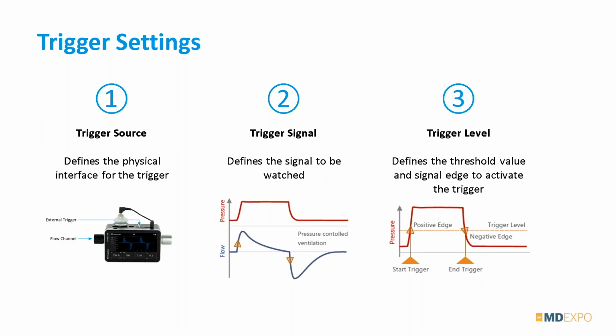There are a handful of ventilators on the market that have a trigger output. They can tell you with a digital signal when they start an inspiration phase and when they change to exhalation, so you can also use that digital signal. But very typically you have a measurement on the gas flow analyzer that you want to use for triggering. Then you can select the signal, typically the flow waveform, or you could also use the pressure waveform.